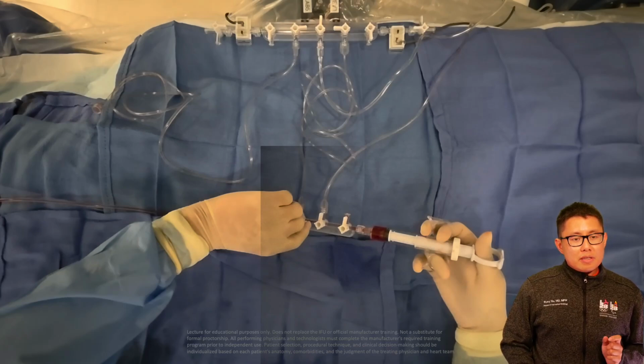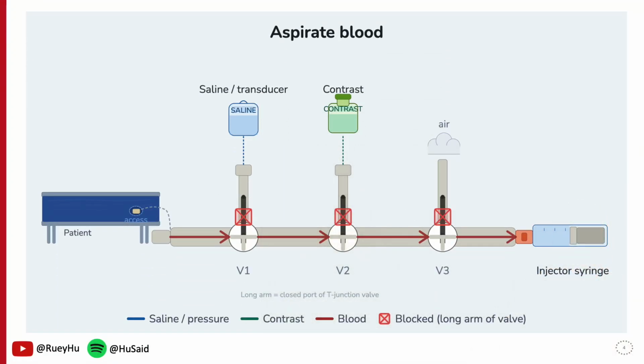Now let me go through the common steps systematically using our diagram over here. So in this diagram, you see V1, V2, V3. You see our T-junction valves, where the long knob, which I indicated in the black, is the blocked side, which I indicated with the red cross box. Okay, so in this default position, V1, V2, and V3 all have the blocked arm, which is the long arm, pointing up. So the T-junction valves all connect to each other. You now have a direct connection between the patient and the injector syringe. So the blood, which I indicated in the red arrows, is flowing freely. You can apply negative pressure by pulling back on the injector syringe to aspirate the blood.